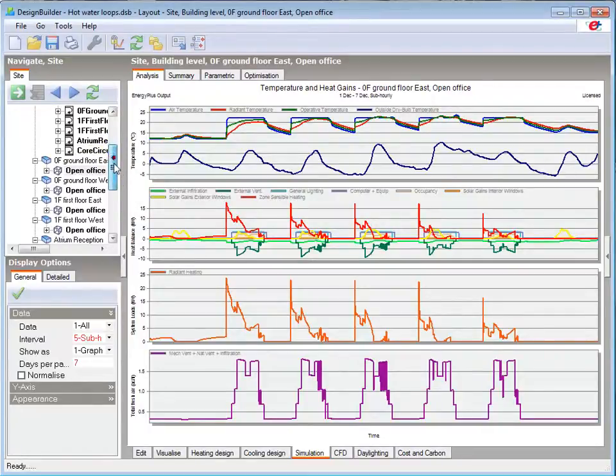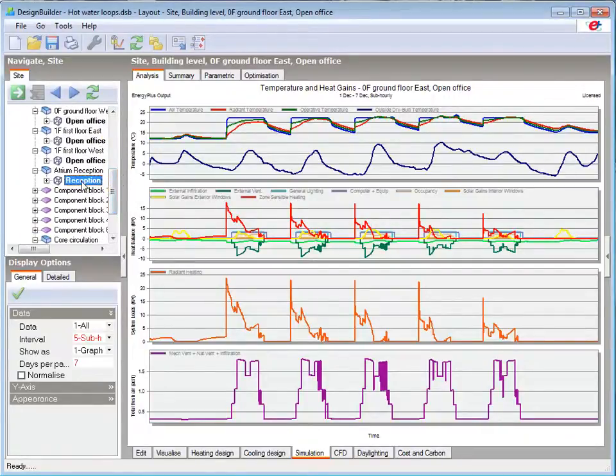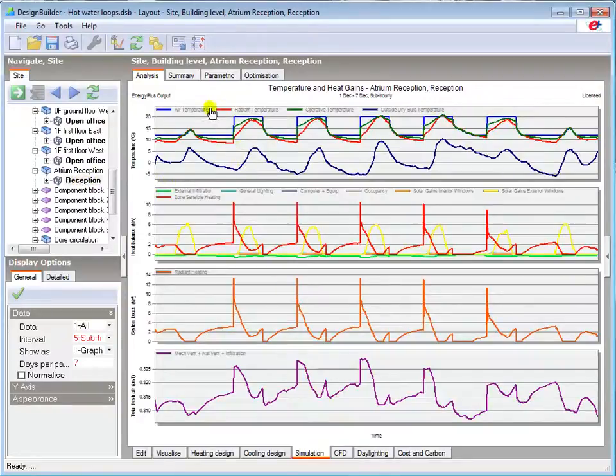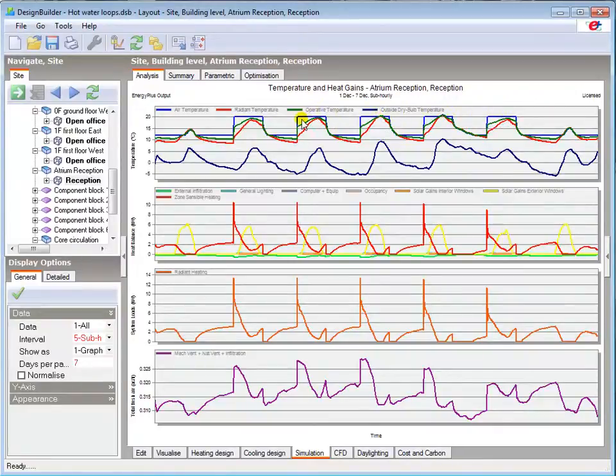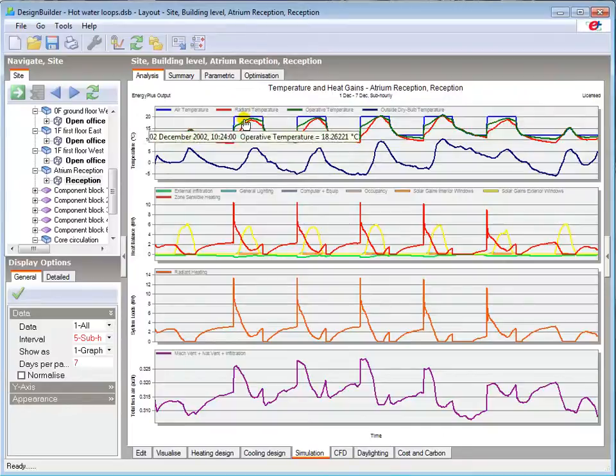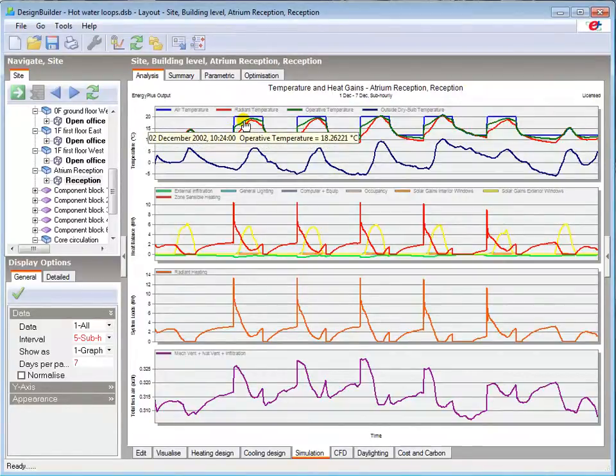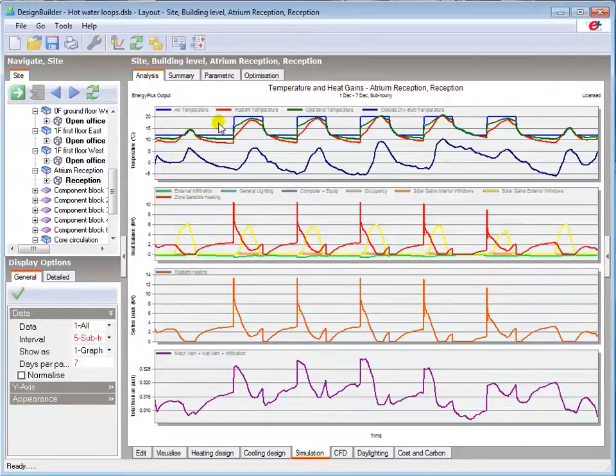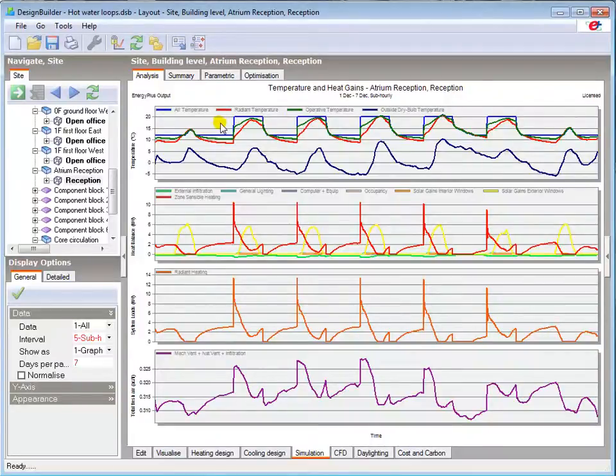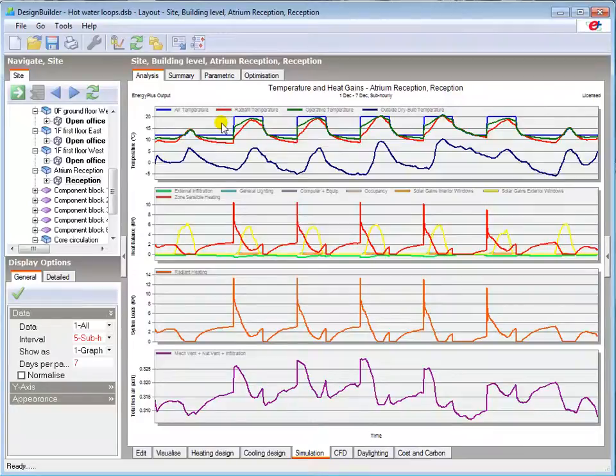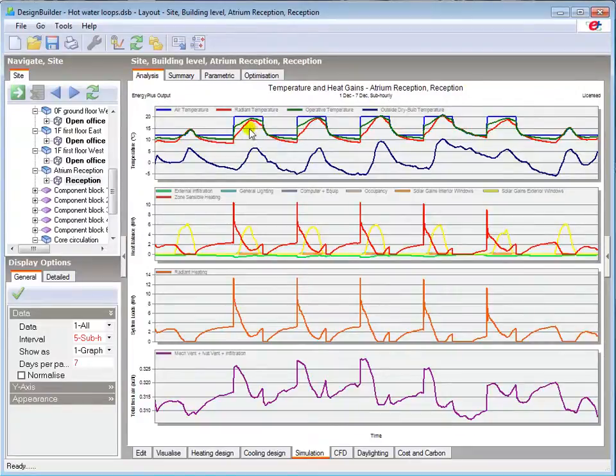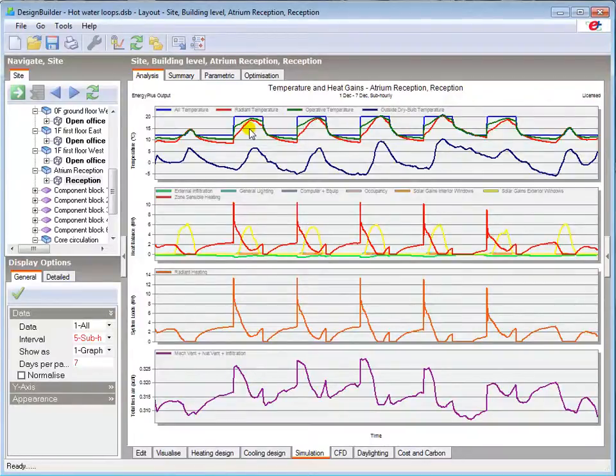Going to the reception zone, you can see that although the air temperature is controlled to the 20ºC setpoint, it takes a long time for the operative temperature to get anywhere near acceptable comfort levels. If we'd used operative control, the increased heat input at the start of the day would result in zone air temperatures of around 27ºC to offset the low radiant temperatures of the glazing. Other consequences of this would be increased plant sizes and higher energy consumption.